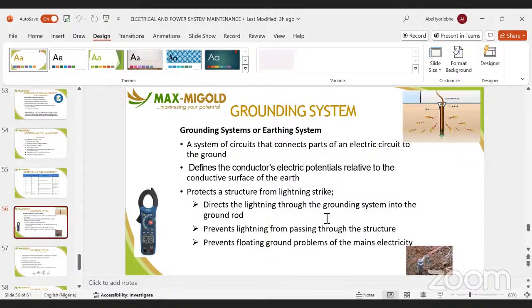Earth is meant to conduct any unusual or abnormal voltage or current to the ground. So the value you can tolerate is maybe 0.002, or 0.2 ohms, as the case may be. The earth is assumed to be at 0 potential; work is not done on the earth, it's assumed to be 0 volts. Anything above that means you need servicing, to lower the resistance so there will be 0 potential in that region.